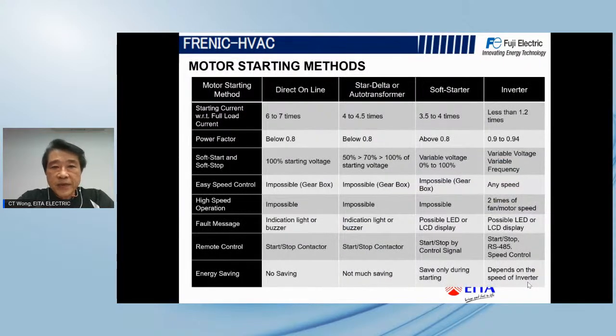Okay, you can see the comparison table over here. That is the direct online, star delta, autotransformer, soft starters, and inverters. We can see the starting current; there is a difference between all the different motor starting methods. For power factor, the inverter will get you the highest. For start and stop, as I say, it is the smoothest, with less mechanical stress to your line, motor, or production line. Because of the VVVF technology, variable voltage and variable frequency, it is easy to control the speed compared with the conventional way, where there is no way for you to control speed. You need a gearbox for that to reduce it.